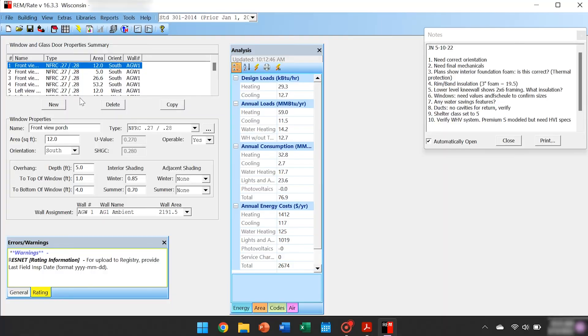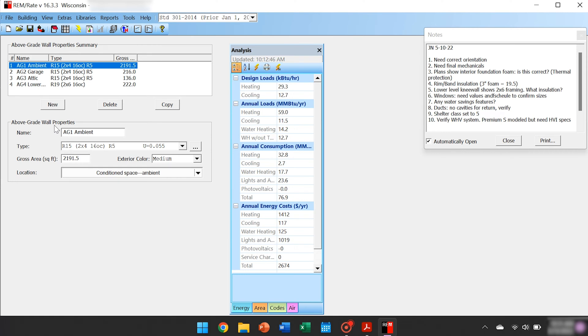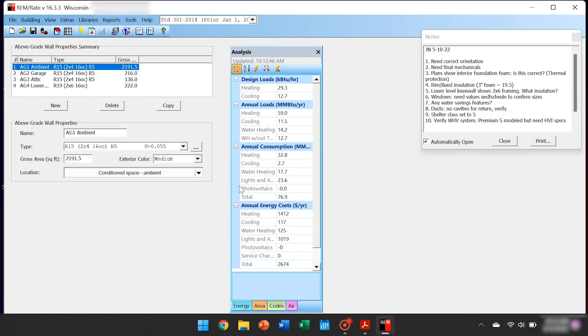Should I run this for you? Right now, let's take a look and see what we have. For the above grade walls, we can pull up that library entry. This particular model has two by four framing with 16-inch on-center framing, R15 in the cavity, with an external one inch of foam at R5. Let's look at what two by six insulation would do with an R23 value for that two by six cavity with that R5, to see what energy changes occur on both the load of the building and the operating cost. The building load right now is 29,300 BTU per hour at design conditions. So now it knocked the load down a little bit and reduced the heating cost by about $100 — total operating cost just a hair over a hundred dollars a year.